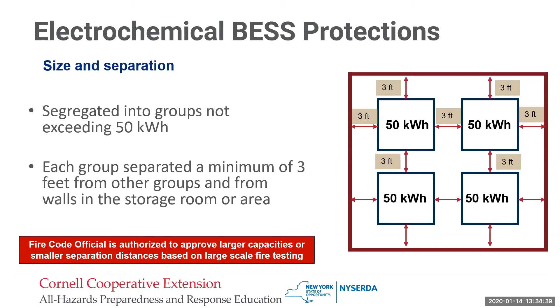Like I was saying earlier, if you dump water all over a bunch of batteries, it's going to permanently ruin them, so you don't necessarily want to do that at first. While it's not a totally directly prescribed pathway, generally what we've seen is it's best to have two types of fire suppression systems: gas or some other non-water type system to snuff out flames initially and stop it.